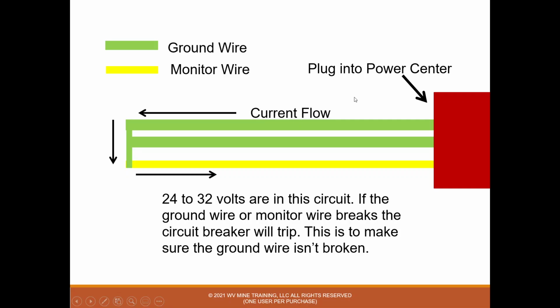So we have here in my little picture, it's coming from the power center, and the green lines here represent a ground wire. And then we have a monitor wire that I have represented as yellow. And we actually have an electrical circuit flowing through that. And it could be 24 to 32 volts. And if either the ground wire or the pilot check wire breaks, then the circuit breaker will trip. This is to make sure the ground wire isn't broken.